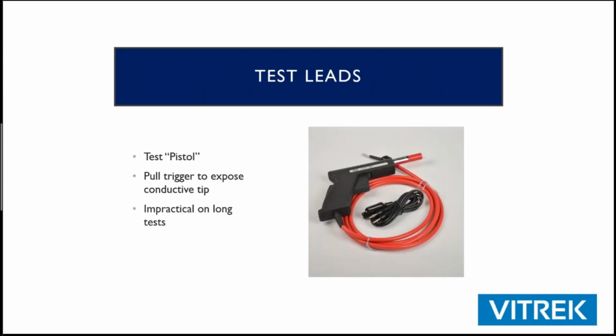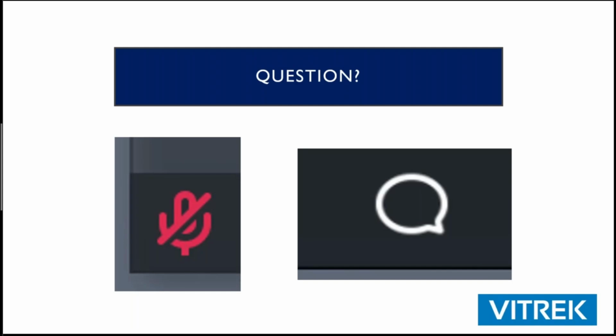If you have a product where maybe you don't have a cord on it, or pigtail wires that are easy to use, you might have to use something like this test pistol. It's relatively safe until you pull that trigger, and then you're going to have an exposed metal probe that extends out. But for some applications like printed circuit boards or sub-assemblies, it's necessary to use something like this. Does anyone have any questions about making connection to their device?